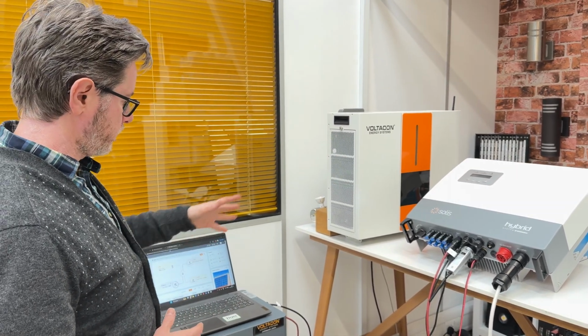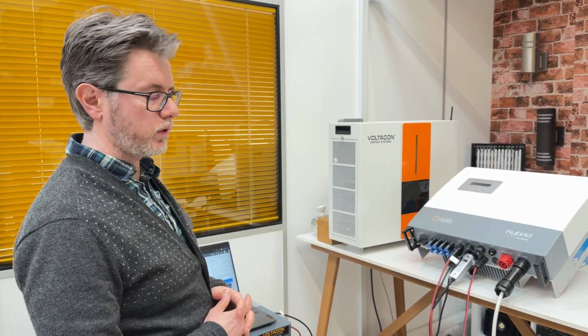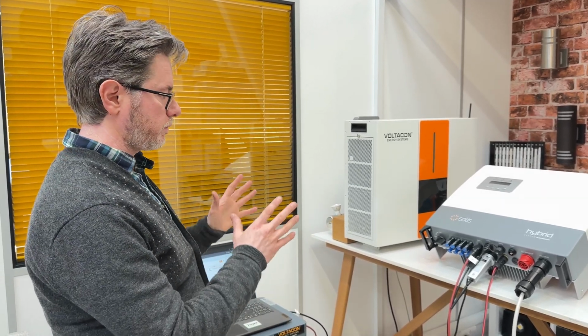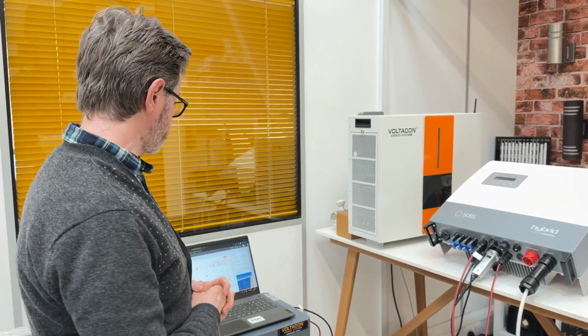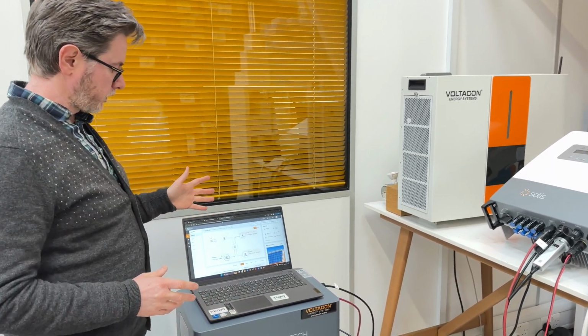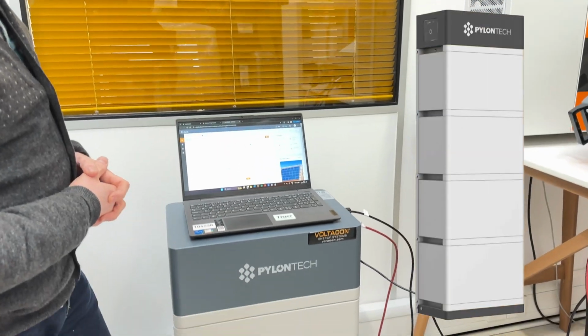Today I'm going to present you the next generation of solar inverters and lithium-ion batteries. We are using in this setup high voltage batteries with Solis hybrid inverters. We set up these units here to work in a self-consumption on-grid application. It is not off-grid. You can set it up as an off-grid as well. But because we are connected to the national grid, all we want to do is to set up the inverter for self-consumption only. Solis is working really well with the Pylontech Force H2.